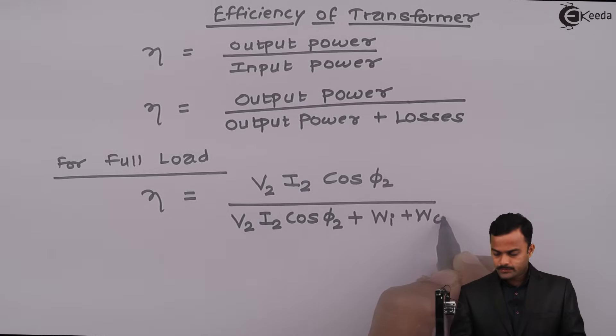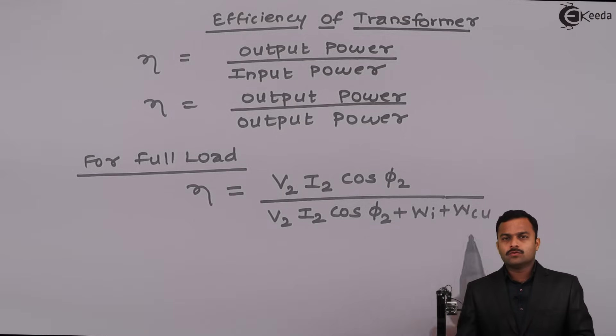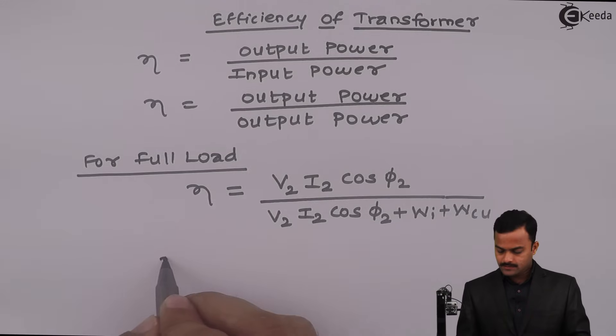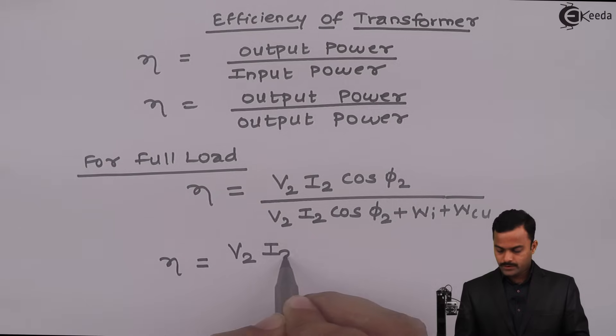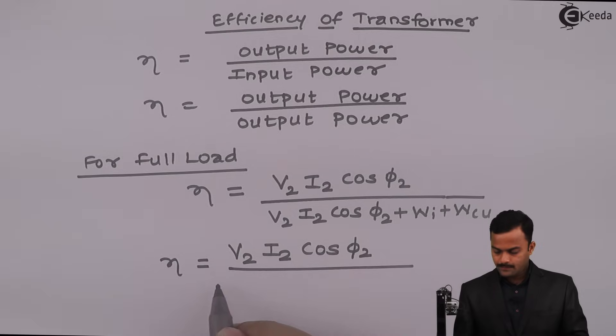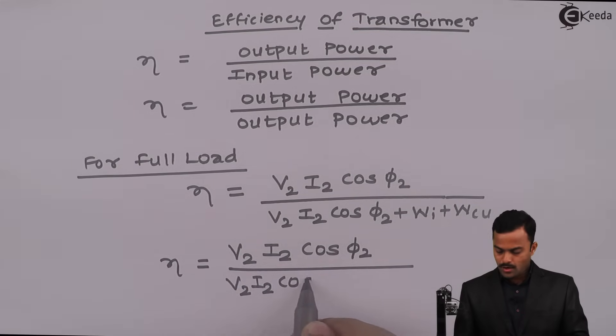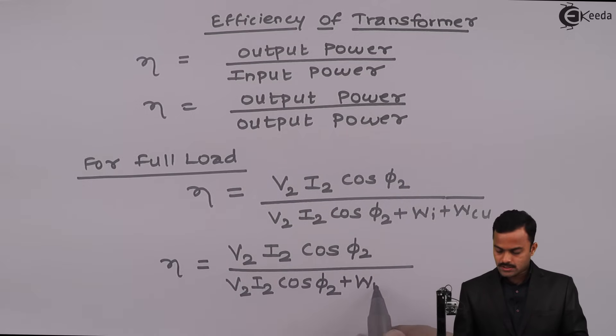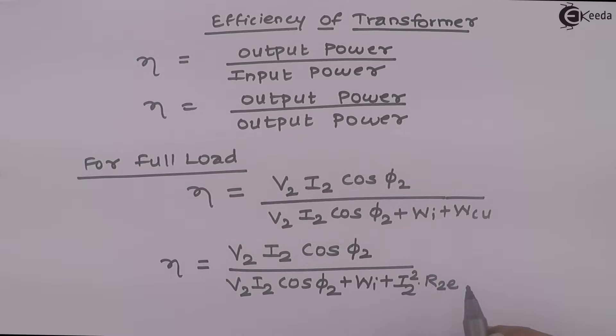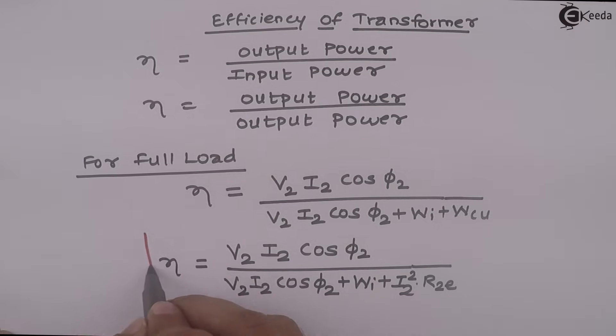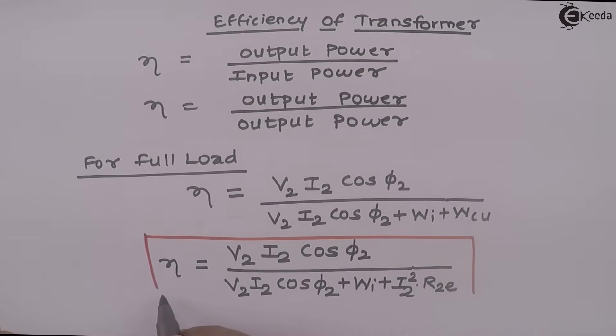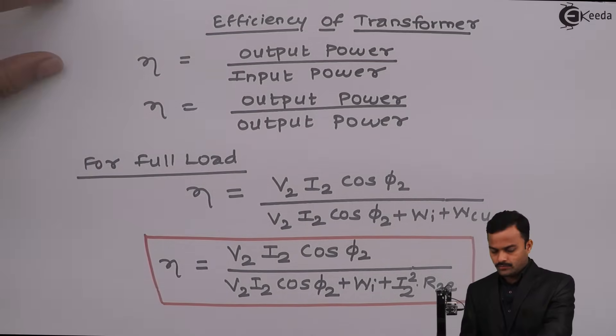So we can write efficiency equal to V2 I2 cos Phi 2 upon V2 I2 cos Phi 2 plus iron losses WI plus copper losses WCu. The copper loss depends upon current so it can be written as I2 squared R2E, where R2E is the resistance referred to the secondary side. This is the formula for efficiency when full load is applied.